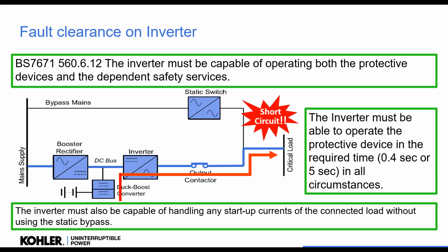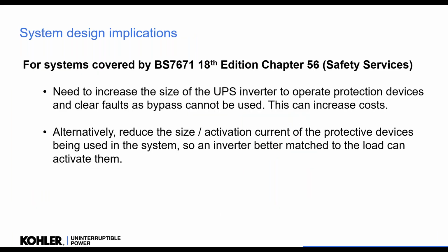Yeah, there's a lot more to go into on this subject. We've done lots and lots of testing with different circuit breakers and MCBs, so we're very confident of what we can do, because everything works differently on an inverter than it does on mains. We need to make sure that we put a big enough inverter in to operate those devices, not using the bypass. So quite often we have to put a much bigger inverter, or UPS, in to do that. We should be using the smallest, fastest circuit breakers we can in the distribution, so we can limit the size of the UPS you need to buy. But do speak to the manufacturer and be comfortable that they can size it accurately and have tested it.